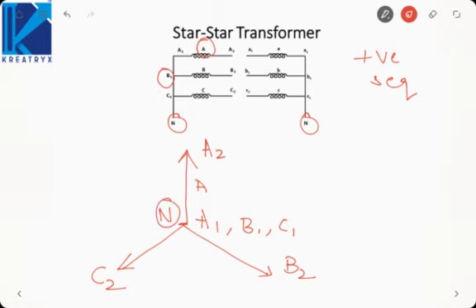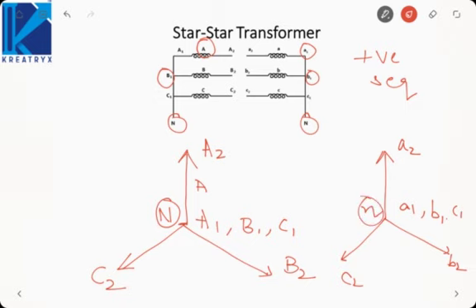Okay. Now the secondary phasor will be drawn in parallel to the primary phasor. So it will be like this, A2, A1, then A1 is connected to B1 also, it will be B2, then C2, this is C1. Okay. Now this point is neutral on the secondary. Here I am denoting neutral by small n because it is the secondary winding.